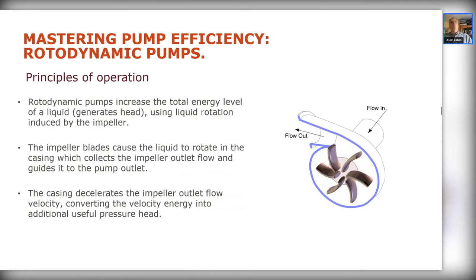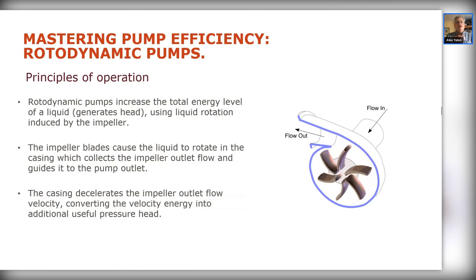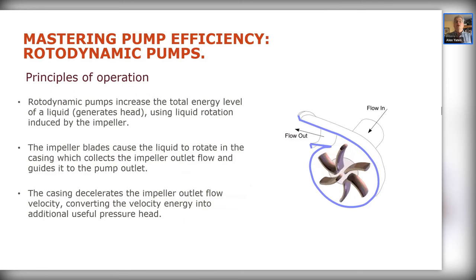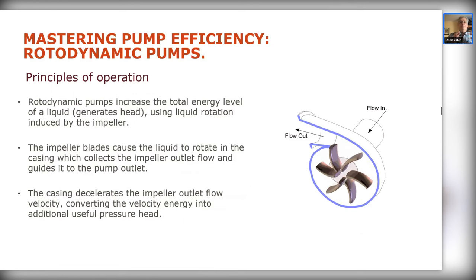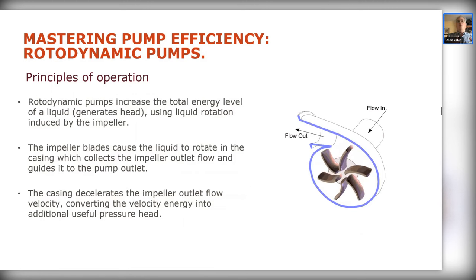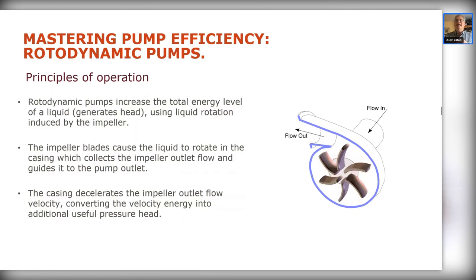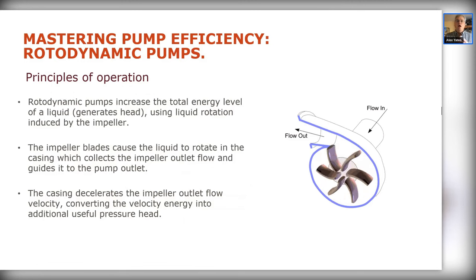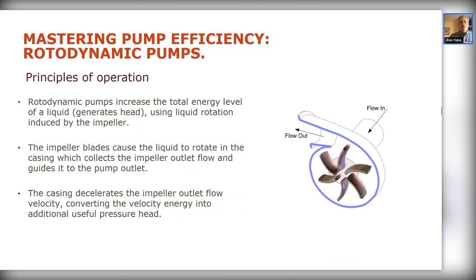We absolutely should be maintaining pump operating efficiency within the pump operating envelope. When looking at how rotodynamic machines fundamentally work: liquid approaches the pump, enters the impeller inlet, pressure drops inside, the liquid rotates, and the impeller and casing work together. The impeller rotates the liquid; the casing collects that rotating liquid and converts rotational energy into useful pressure energy.